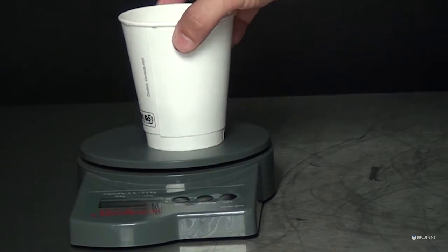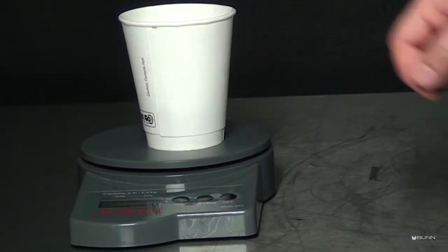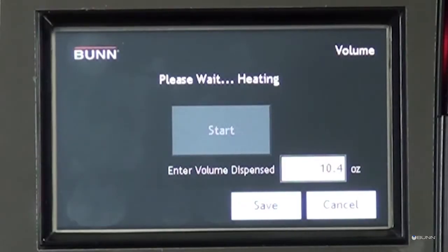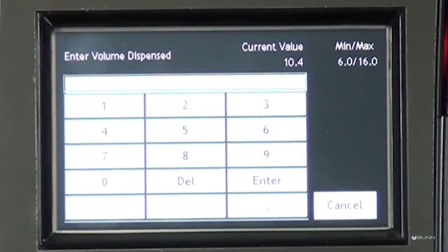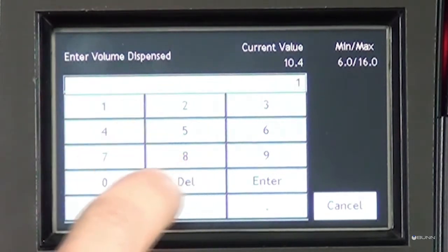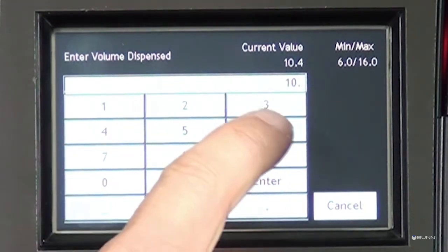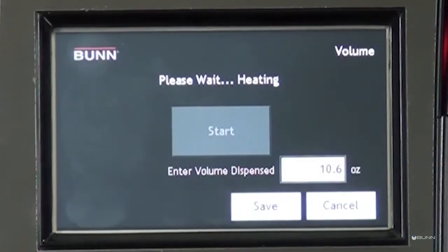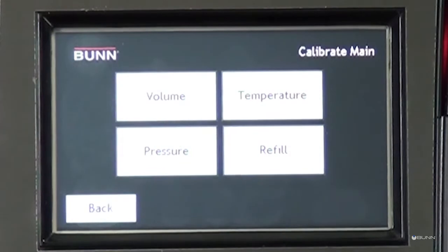When cycle finishes, weigh filled container. Subtract first measure from second to get the net weight of water. Repeat procedure at least 3 times to get an average volume. Press the white volume dispensed box. Enter in the average weighed volume. Press enter. Verify or adjust cup volumes if needed. Press Save to retain the new setting.